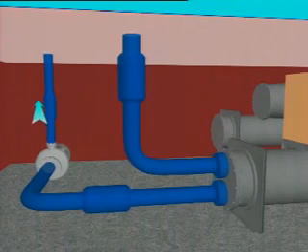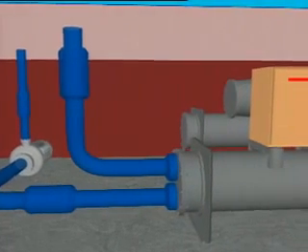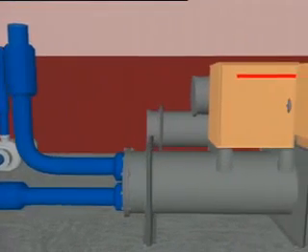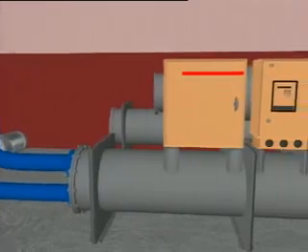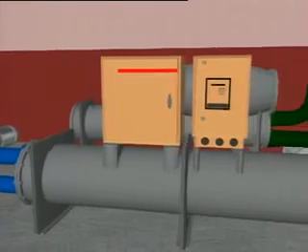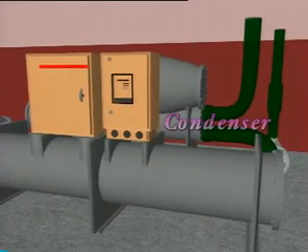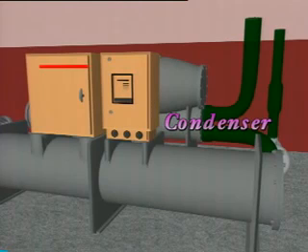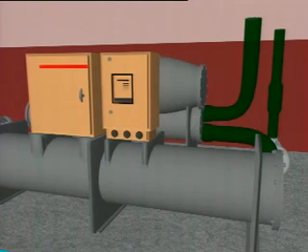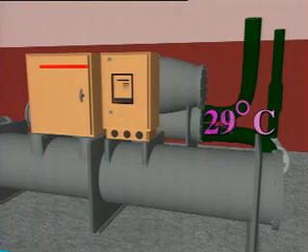The heat transferred to the refrigerant will be passed to the condenser water circulating through the condenser. After absorbing heat from the refrigerant, the condenser water temperature will be raised from about 29 degrees Celsius to 34 degrees Celsius.